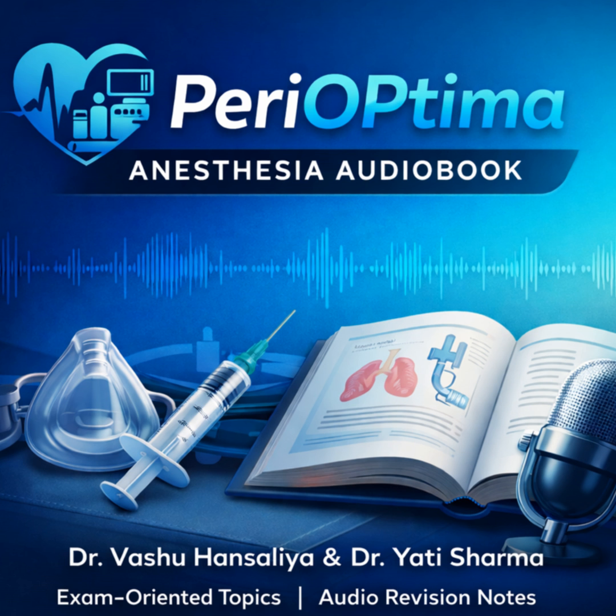What does that mean in practice? Imagine your pipeline is working fine. You have 50 psi of oxygen pressure coming into the machine. But you, the doctor, reach over and turn the oxygen flow meter knob to 0. The fail-safe valve sees 50 psi of pressure, so it stays open. It will happily allow you to deliver 100% nitrous oxide because the supply pressure is fine. The fail-safe does not protect against user error at the flow meter.